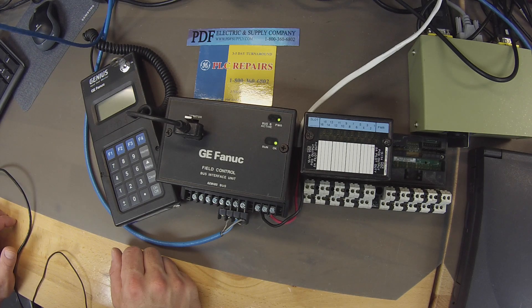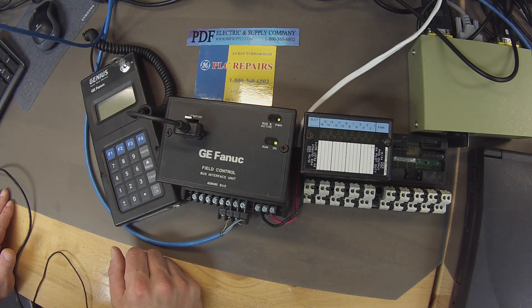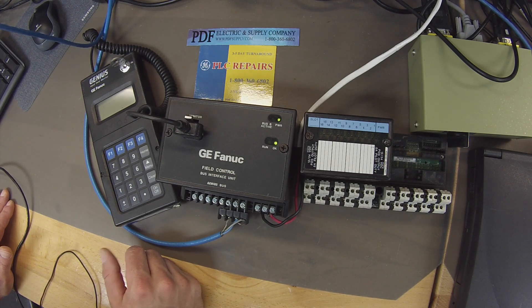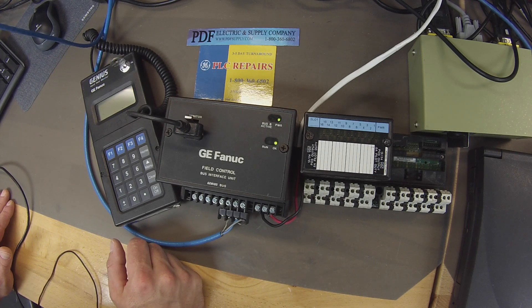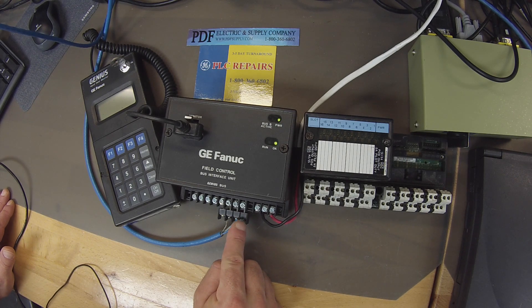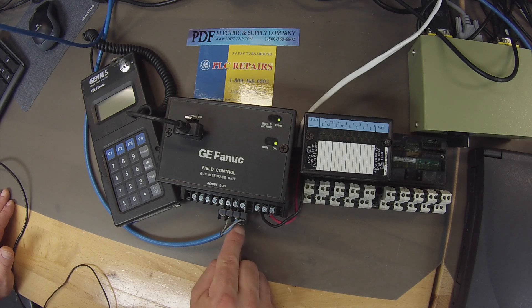Just a quick description of what I have here. On the 9030 side, I'm using a PWR330 power supply, a CPU374 plus and a Genius Bus Controller, that's the IC693BEM331. I have it attached to an IC693CHS397 five-slot rack. For this test, you're welcome to use a different processor or different rack, but you will need to have the Genius Bus Controller. I have the Genius Bus Controller connected to my GBI through the serial A1 and A2, and I also have a shield. Make sure that you have a resistor — I'm using a 150 ohm resistor in between A1 and A2.